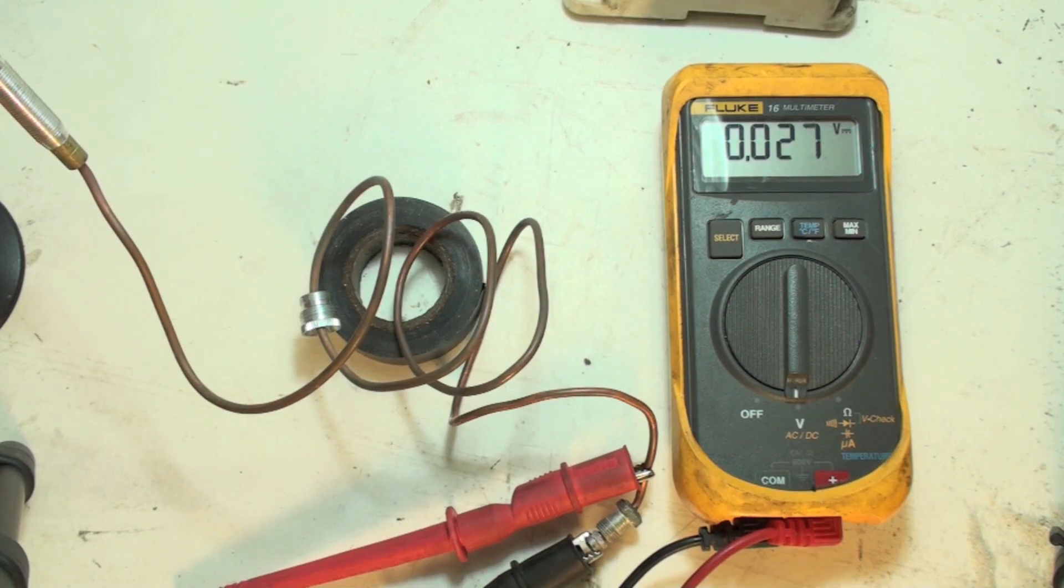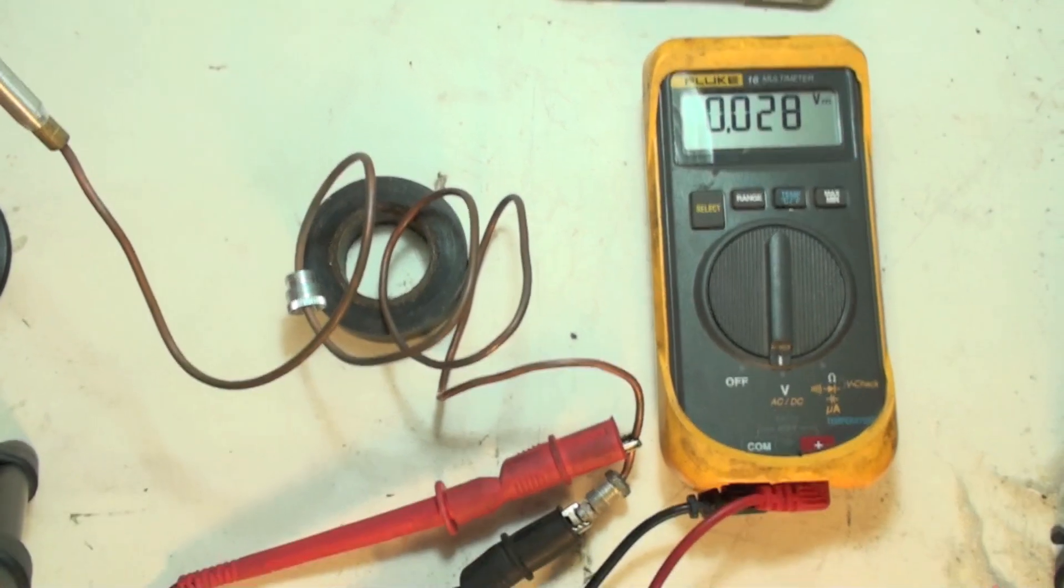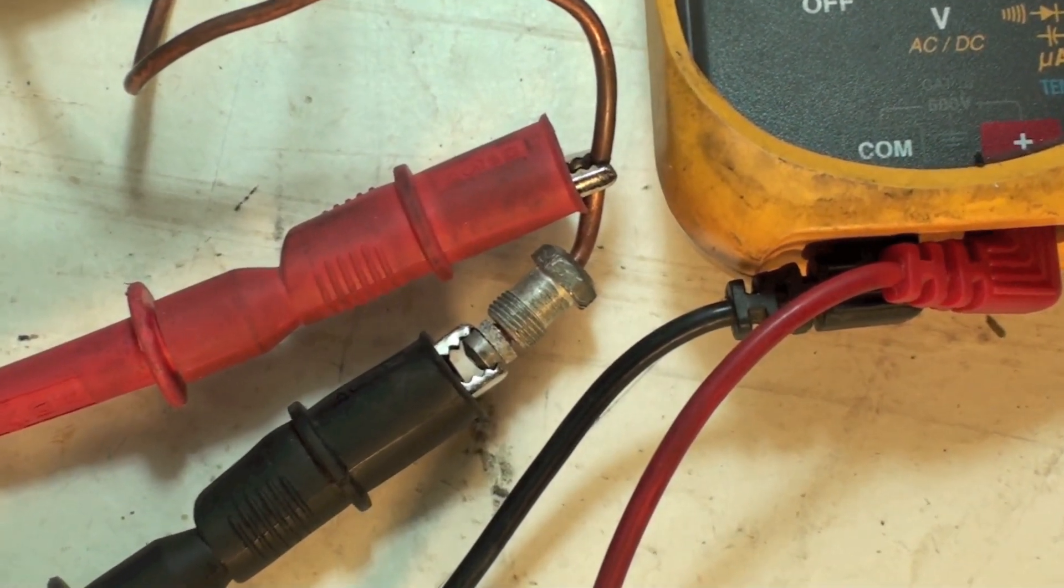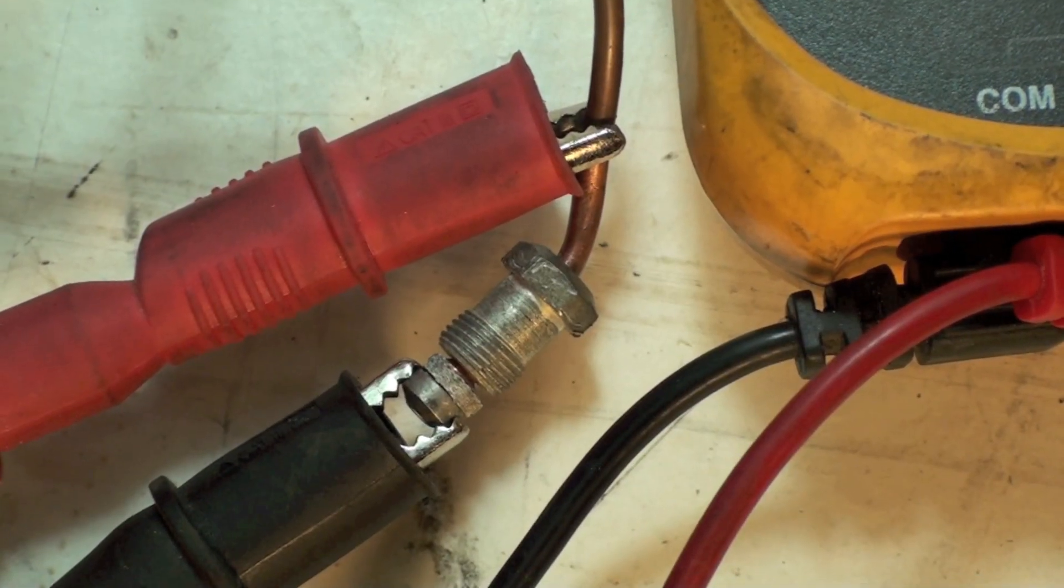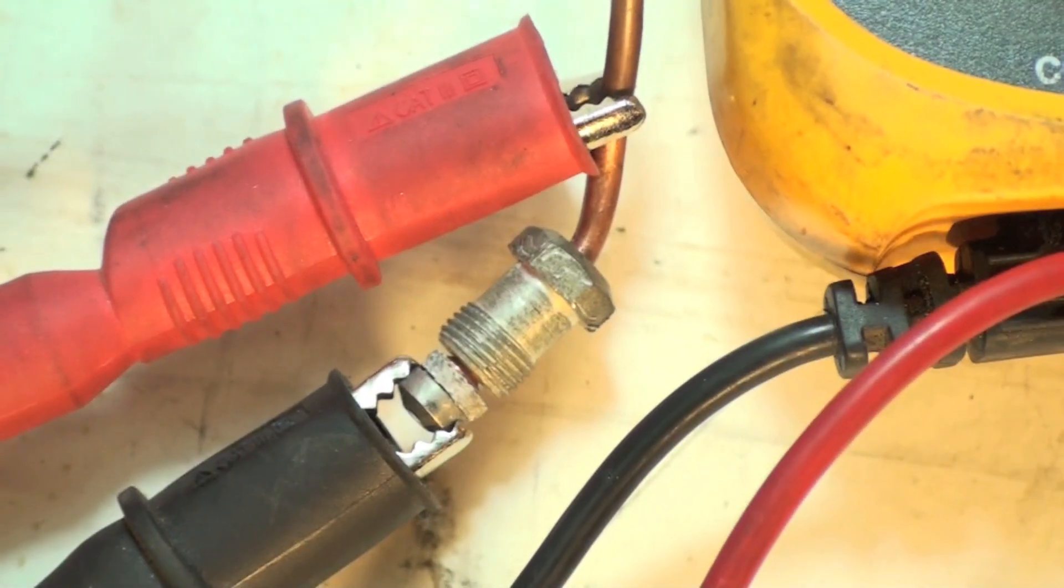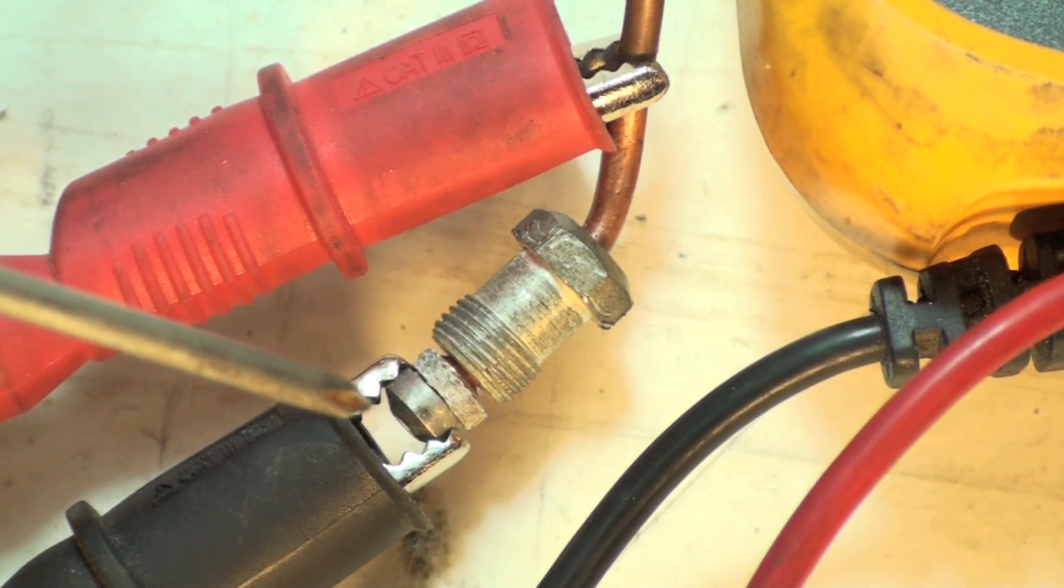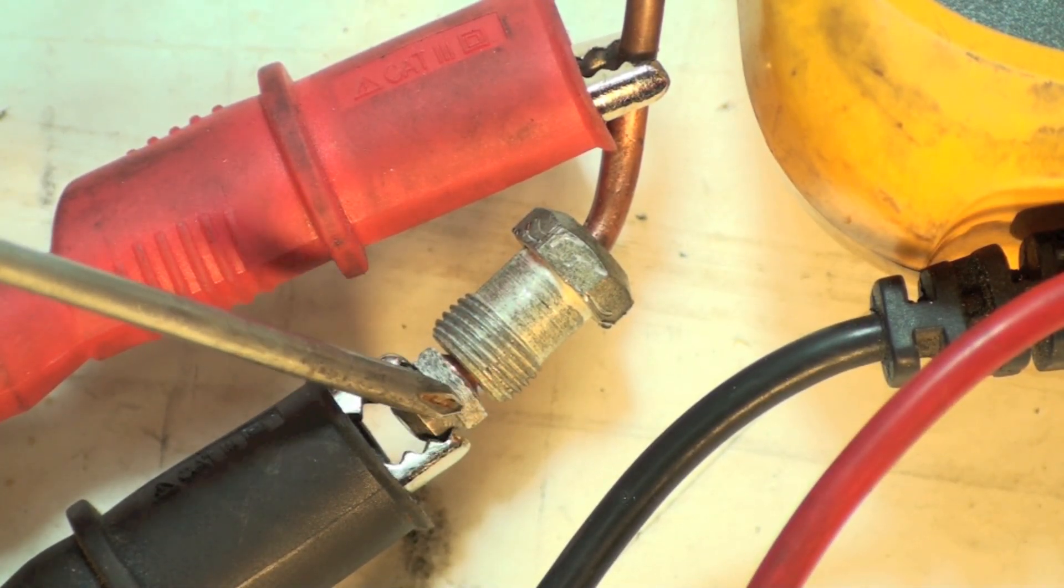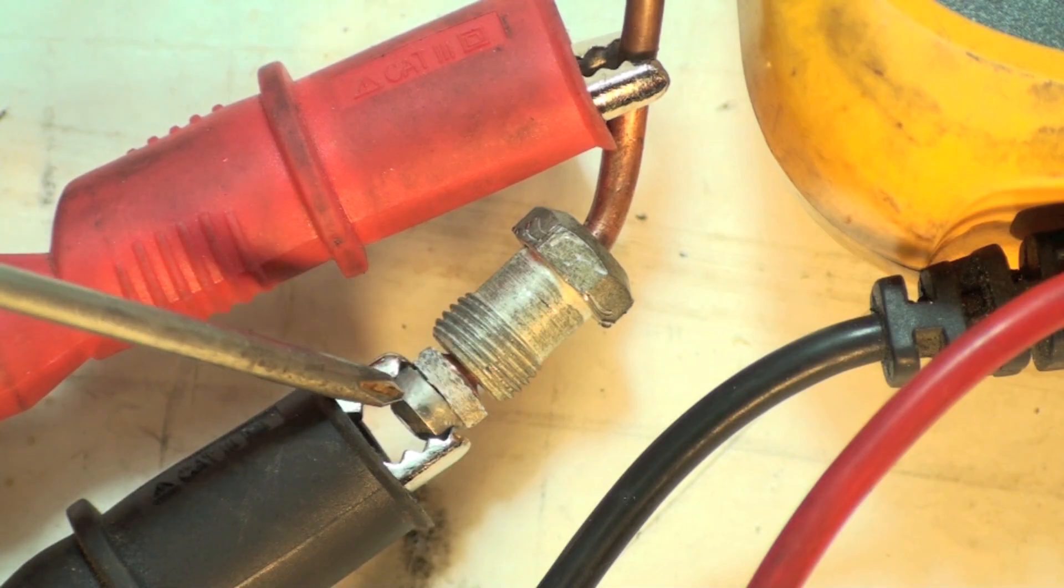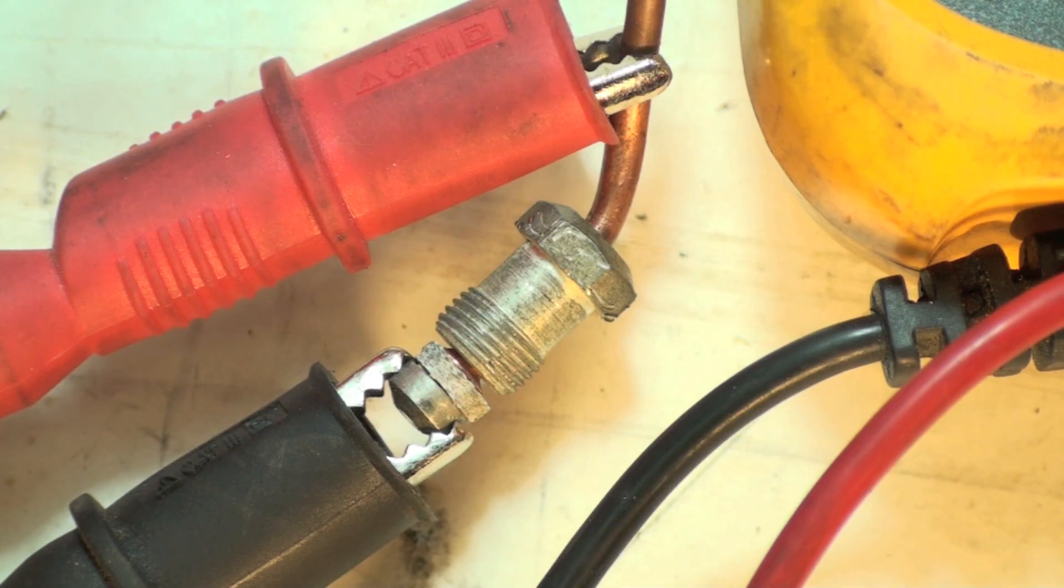Okay, so we're sitting about 27 now. I'm going to show you the way we hook these leads up. This is important how these leads are hooked up. You can see in this black one there's a little insulator right here. You want it on the button, not past the insulation. You don't want it up here someplace, you want it down here. And then the other one can just be on the copper tube and it'll read whatever millivolts this thing's putting out.